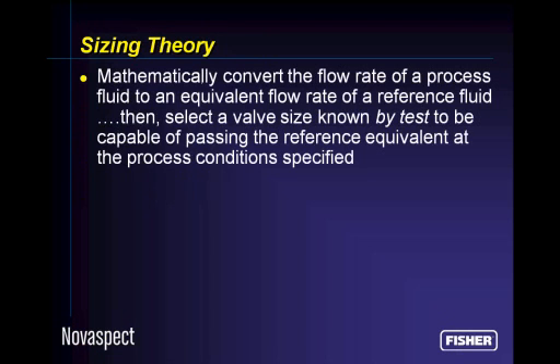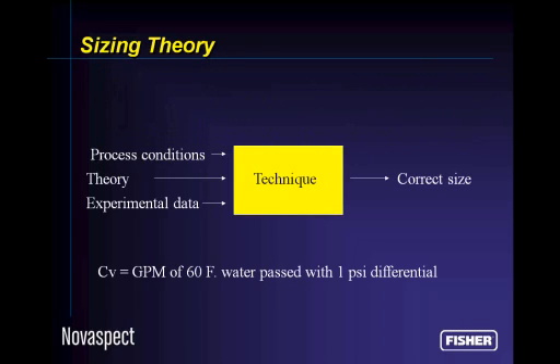So how do we size? Well, the sizing theory is that we mathematically convert the flow rate of a process fluid to an equivalent flow rate of a reference fluid, which happens to be water. And then select a valve size known by test to be capable of passing the reference equivalent at the process conditions specified. This is it.